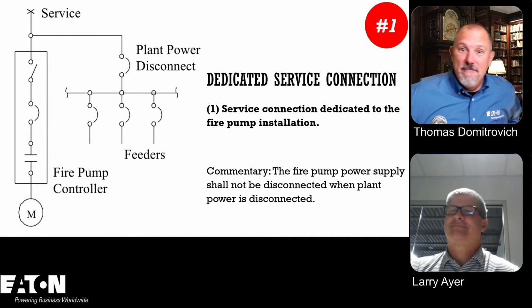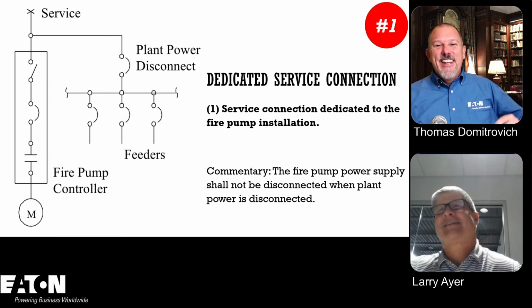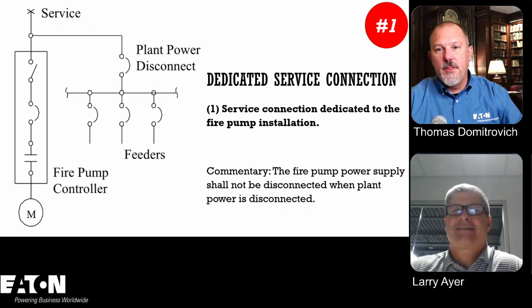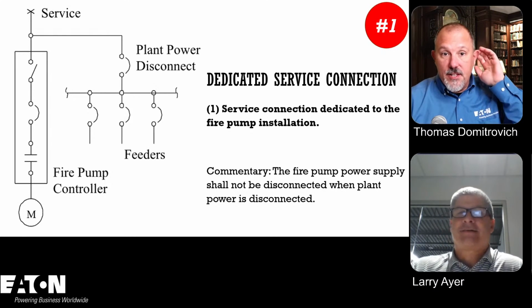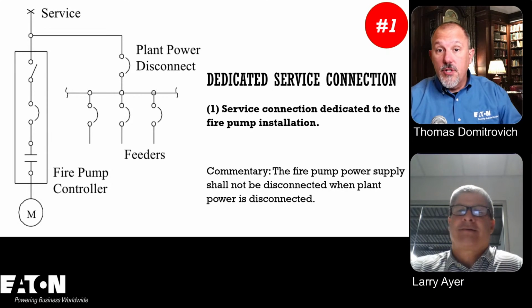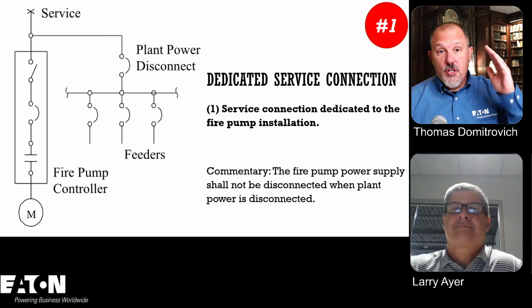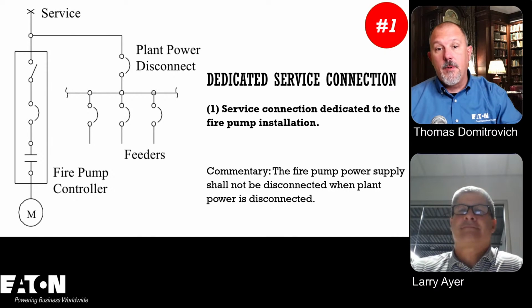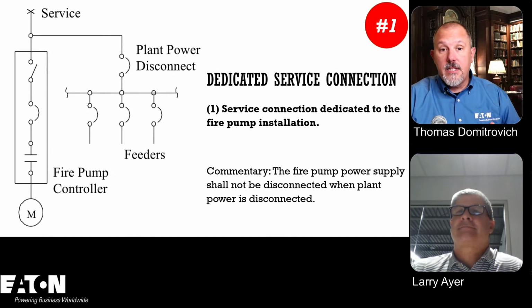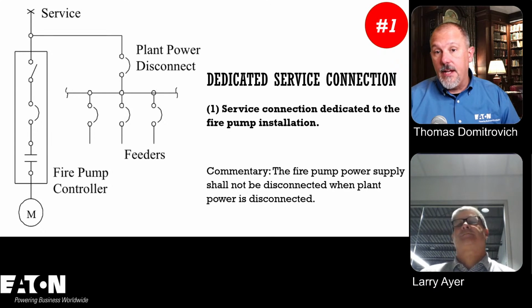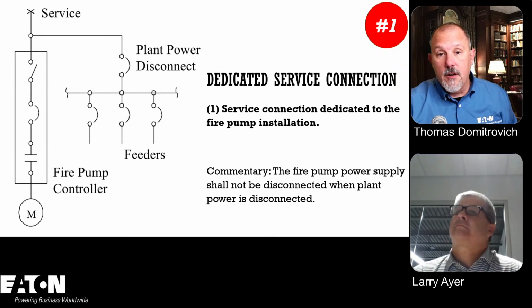That's right. So what we're going to walk through next are the different options, right? So this is your dedicated service connection, which is probably your simplest application, where you're just coming straight off that service and coming into the fire pump controller. The fire pump controller will be service entrance rated and listed with all your bonding and all that good stuff in there. And then you'll go down to the fire pump. So a very simple solution.